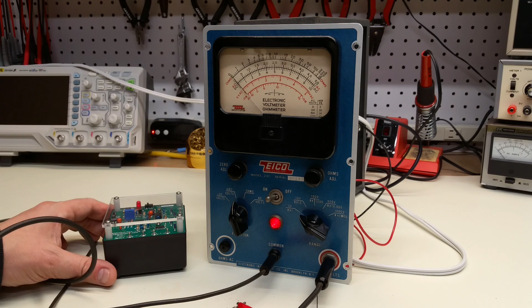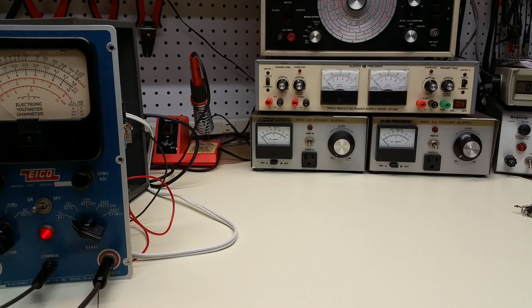And then when we go to calibrate the AC, we're going to use one of these BK Precision Model 1653 isolated power supplies, AC power supplies. So we'll set that to 100 volts or whatever we want according to a DMM, and then we'll use that as a calibrated, known source for the EICO.